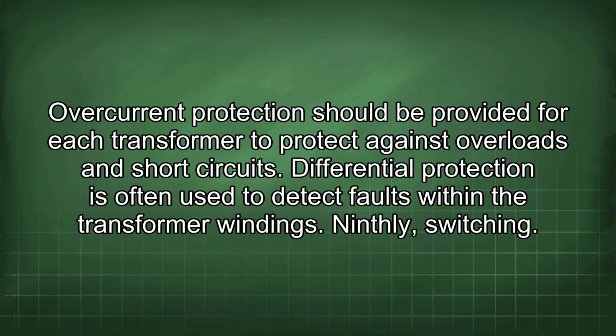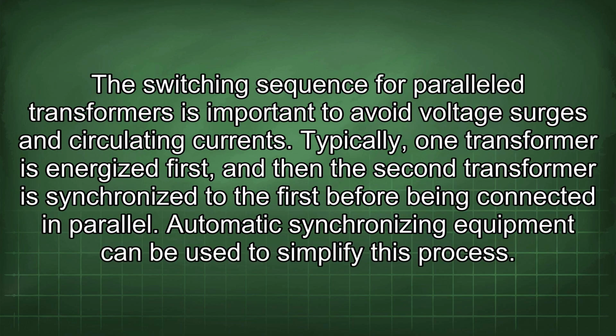Ninthly, switching. The switching sequence for parallel transformers is important to avoid voltage surges and circulating currents. Typically, one transformer is energized first, and then the second transformer is synchronized to the first before being connected in parallel. Automatic synchronizing equipment can be used to simplify this process.